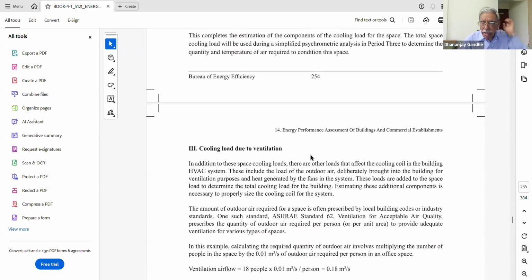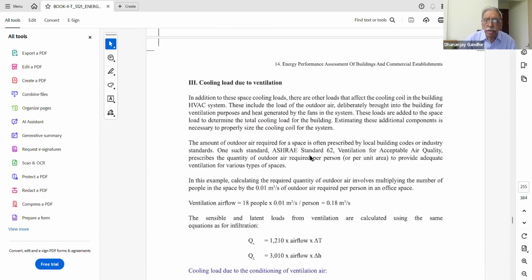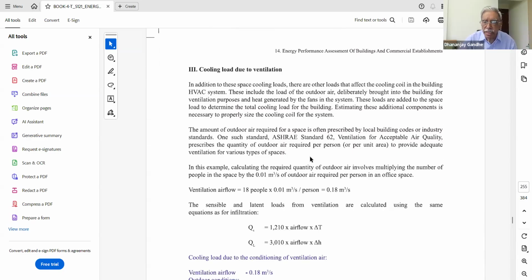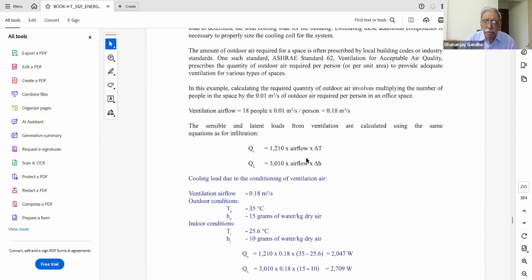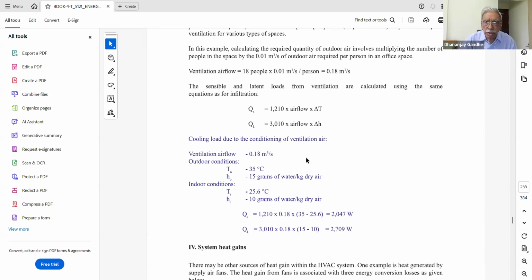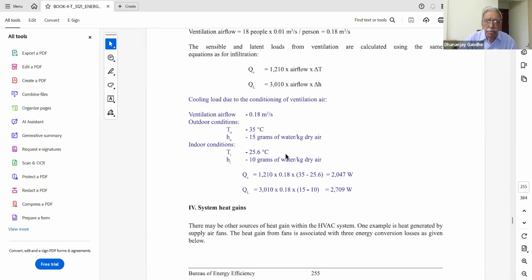And then there are some additional input heat gains. One is the heat load due to ventilation. That is also to be considered. So these calculations are also mentioned here on how to calculate the heat load of the ventilation. Now, what is ventilation load? In an air conditioning system, you have to periodically supply some fresh air.